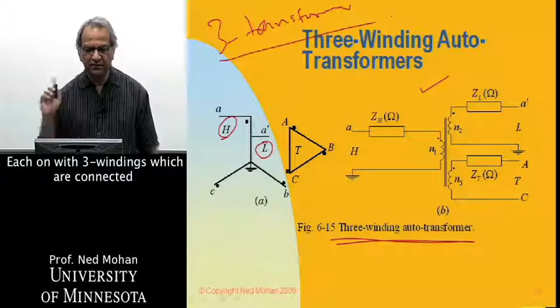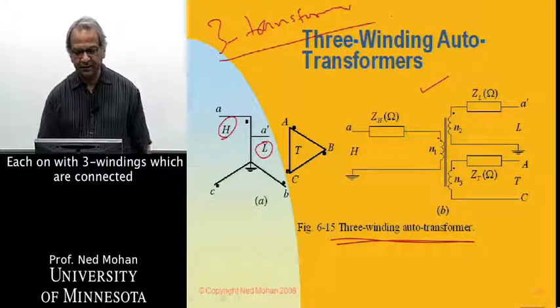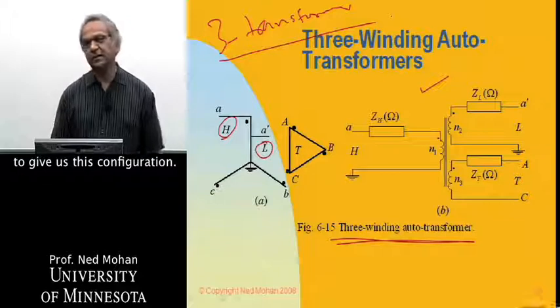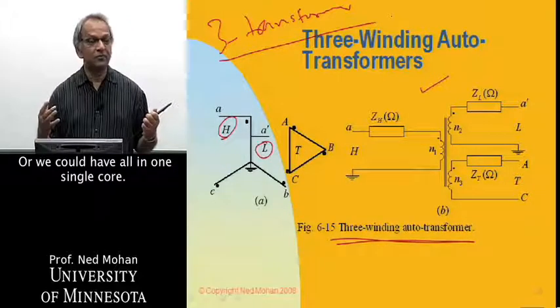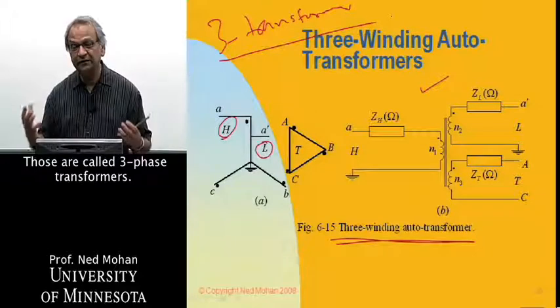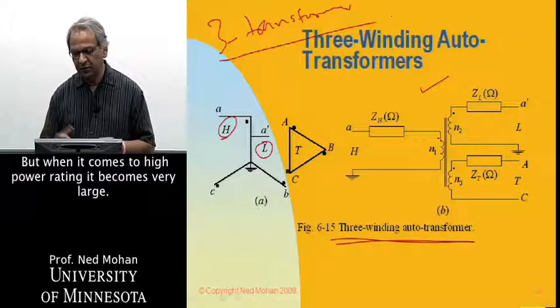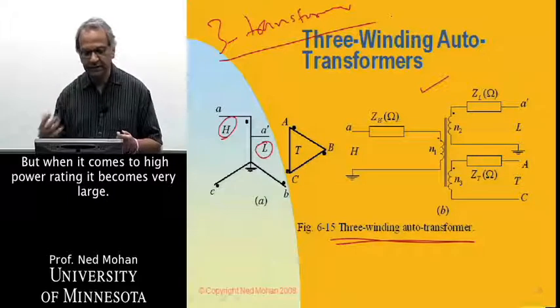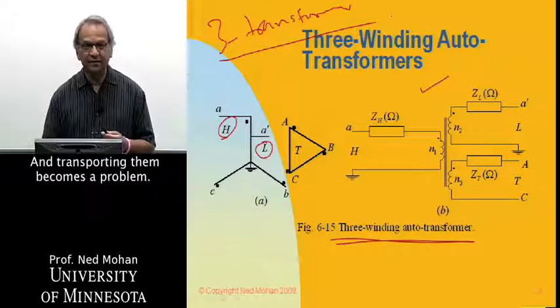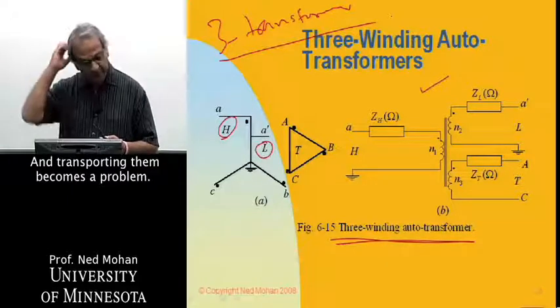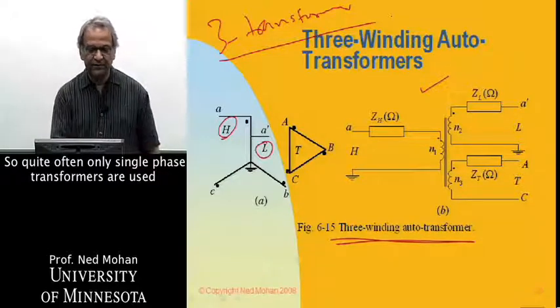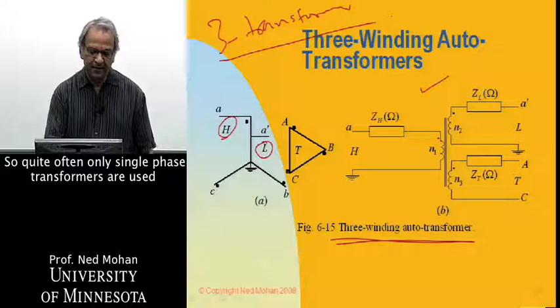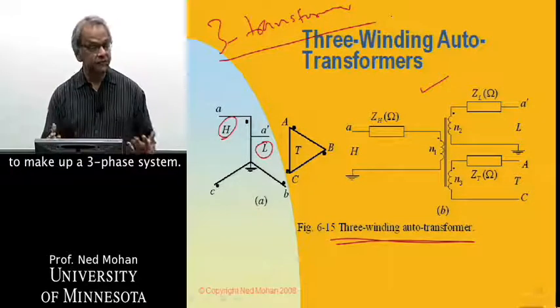But there may be three transformers, each one with three windings, which are connected to give us this configuration. Or we could have all in one single core. Those are called three-phase transformers. But when it comes to very high power rating, it becomes very large, and transporting them becomes a problem. So quite often, only single-phase transformers are used to make up a three-phase system.